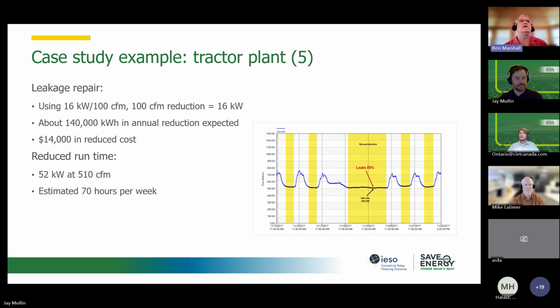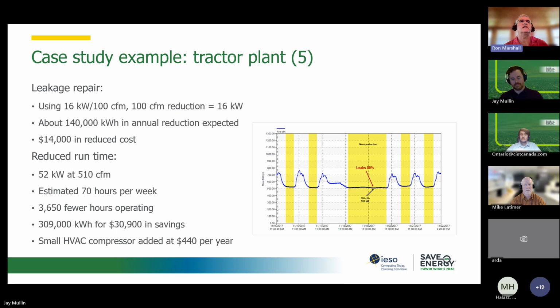right? So when we calculated the leakage repair, we assumed this system could be running at 16 kilowatts per 100 CFM, not including the dryer, and we calculated out they could save $14,000 in leakage costs, right? If we reduce the downtime, or sorry, the runtime of the system, there's an additional 40% savings because the compressors would not be running, 3,650 hours less operating hours on the compressor, reducing maintenance costs, right? And of course, the small HVAC compressor that would be running added $440 a year.